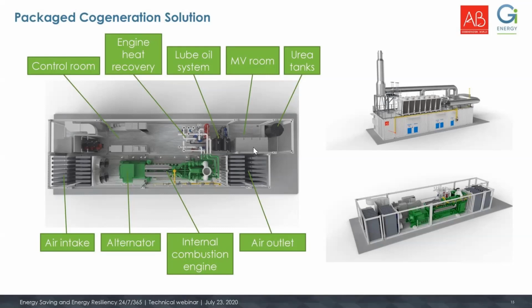We have other balance of plant components that are also pre-integrated in our system and needed for full functionality of the plant: medium voltage components in case we have a medium voltage alternator, or low voltage components; a lube oil management system pre-mounted in the container; urea tanks needed for the exhaust gas treatment system; and a small control room that allows our operator or maintenance tech to take care of the unit and access the control system directly from the package.